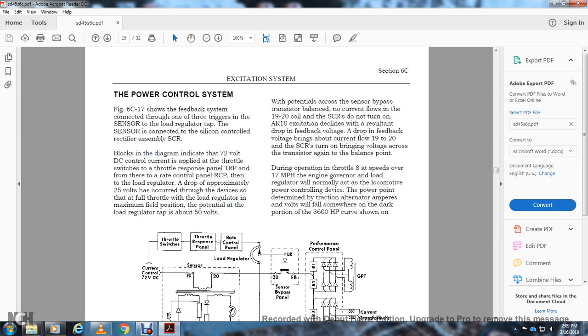Alright, the power control system, figure 6C17, shows the feedback signal connected through one of the three triggers of the sensor of the load regulator tap. The sensor is connected with the silicon controlled rectifier assembly, the silicon rectifier. The block diagram indicated the 72 volt DC control current was applied with the throttle switch, with the throttle response from the TRP panel. Then the rated control panel, RCP.